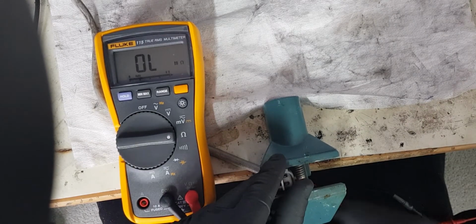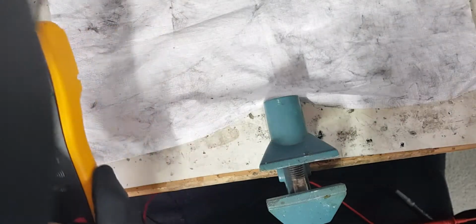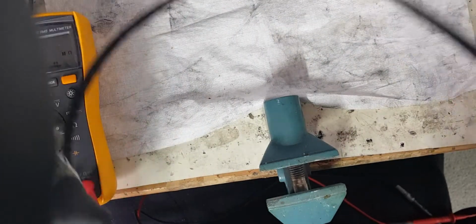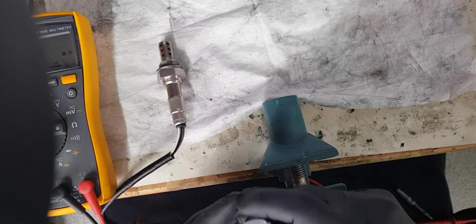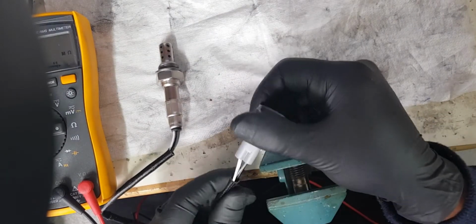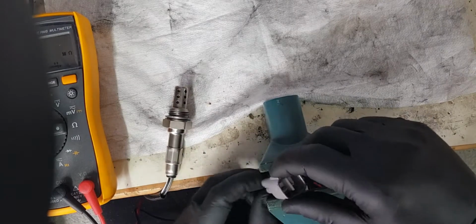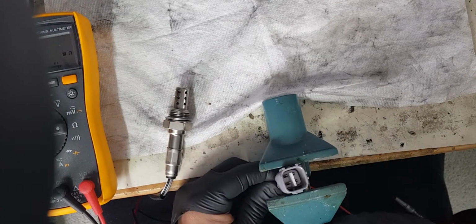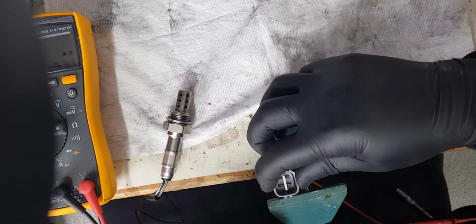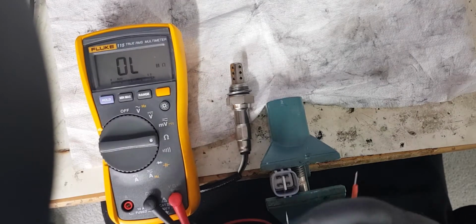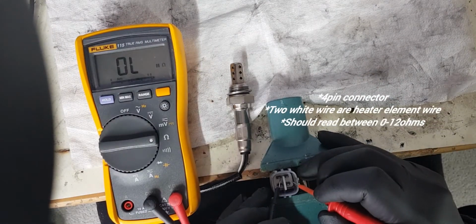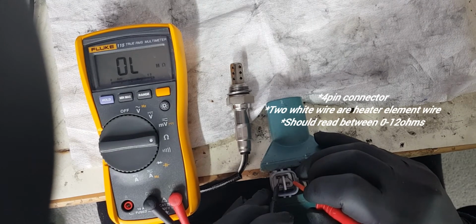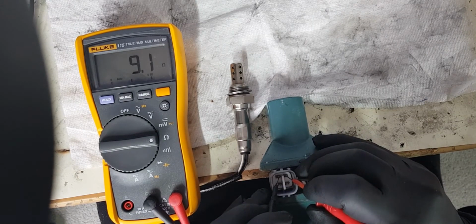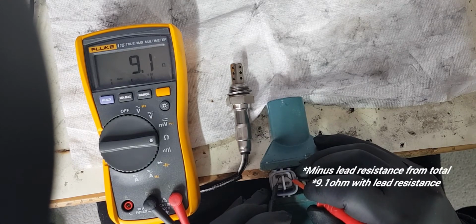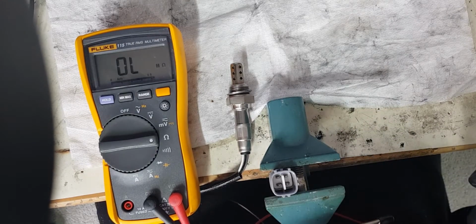So now let's remove the sensor out of the way and bring in the brand new one. We're interested in these two white ones here, on this side. Okay, let's tighten that, and we're still on our ohm scale. I'll probe this in here. This should be below 12 ohms. Great, we'll get 9.1 ohms, so 9 ohms because of my lead resistance, which is good.